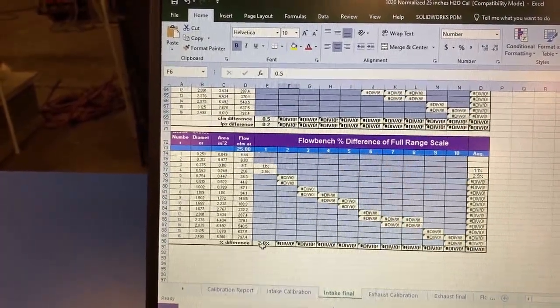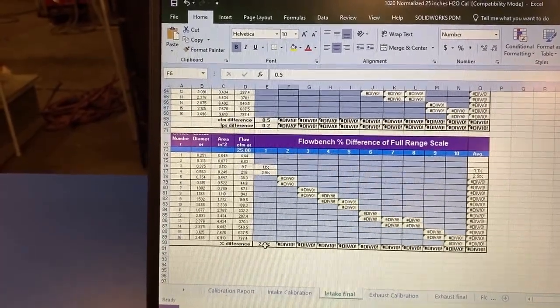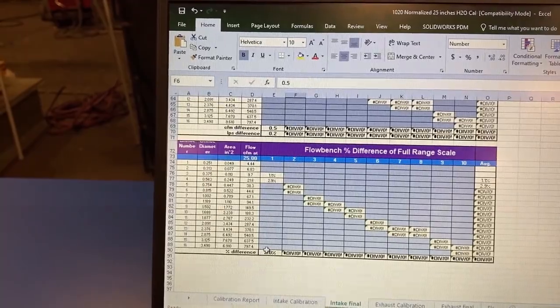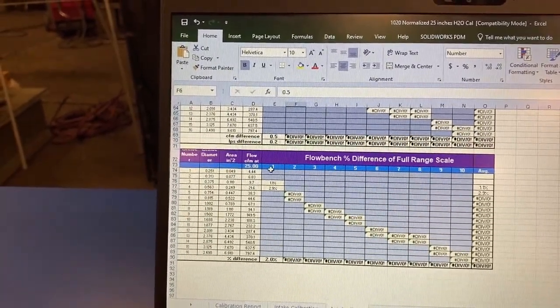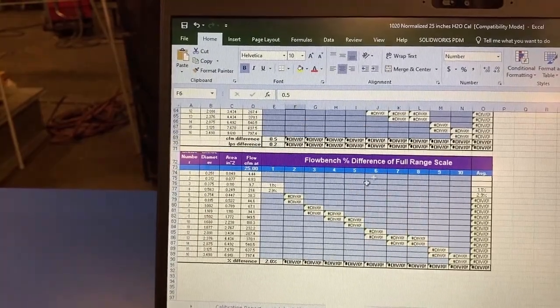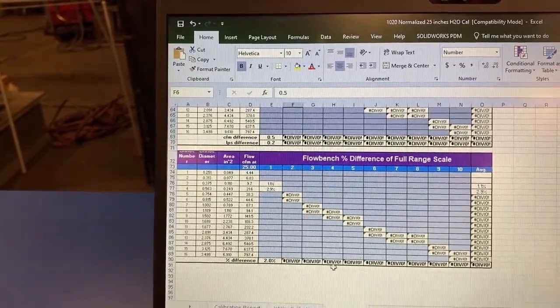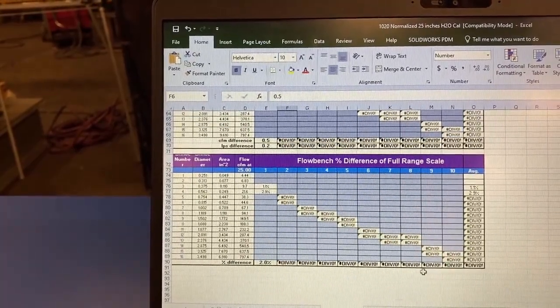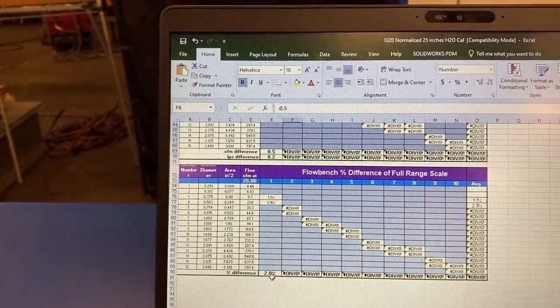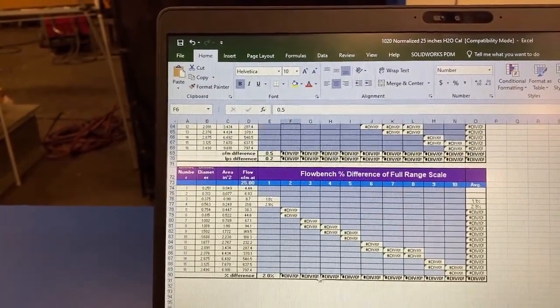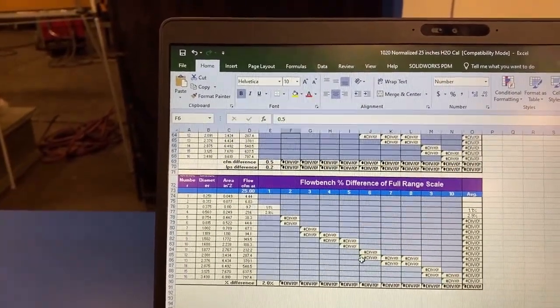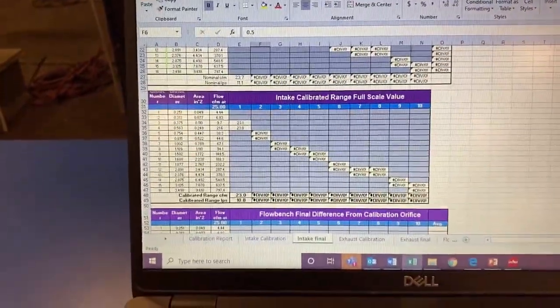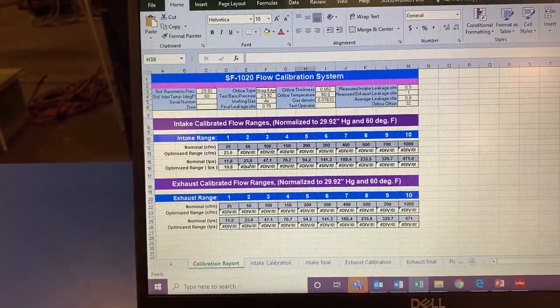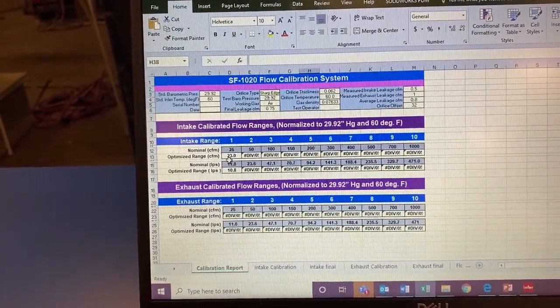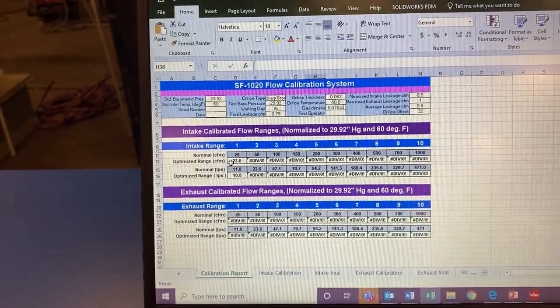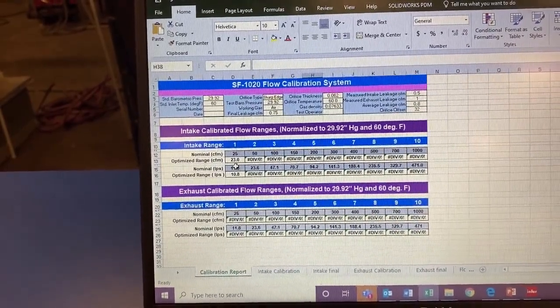And see that this range 1% difference at full range scale is 2%. That is okay for range 1. For every other range, this percentage needs to be 0.5 plus or minus or below. So plus or minus 2% for range 1, plus or minus 0.5% for every other range. Once you have these numbers, you'll come down to calibration report, and you will adjust with this value in the bench. So optimized range CFM is 23 in range 1.